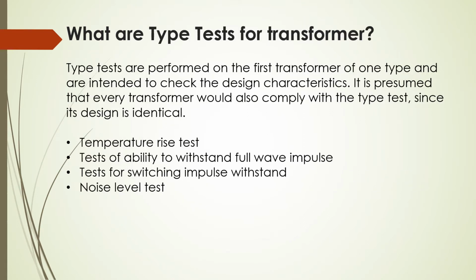What are the type tests for the transformer? Type tests are performed on the first transformer of one type and are intended to check the design characteristics. It is presumed that every transformer would also comply with the type test since its design is identical. The type tests are the temperature rise test, test of ability to withstand full wave impulse, test for switching impulse withstand, and noise level test.